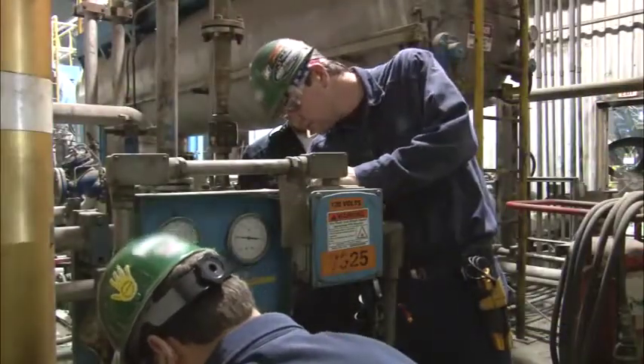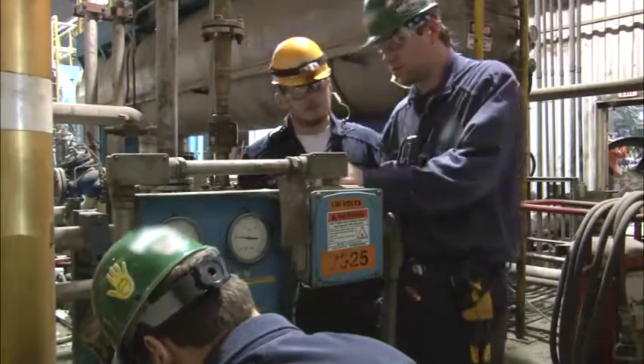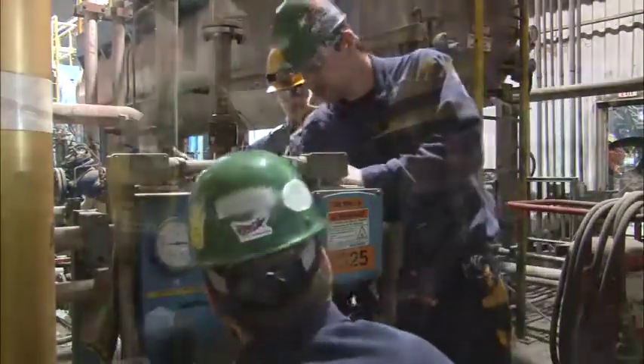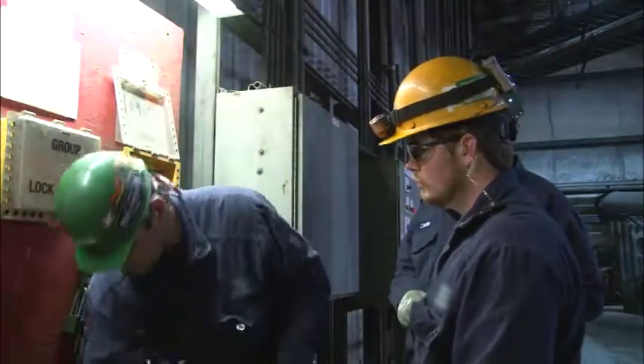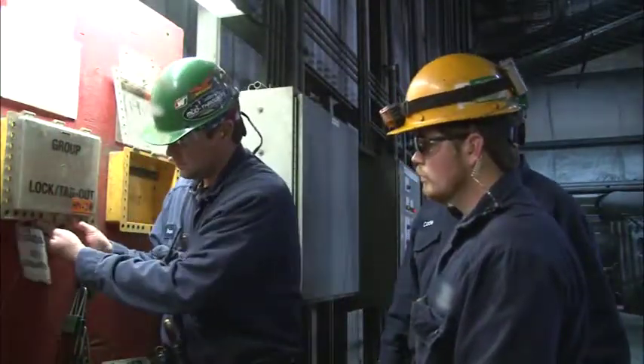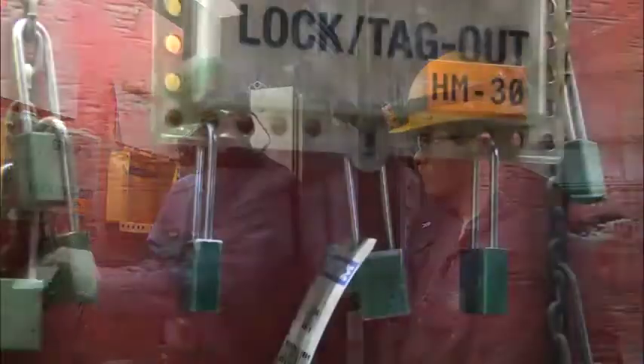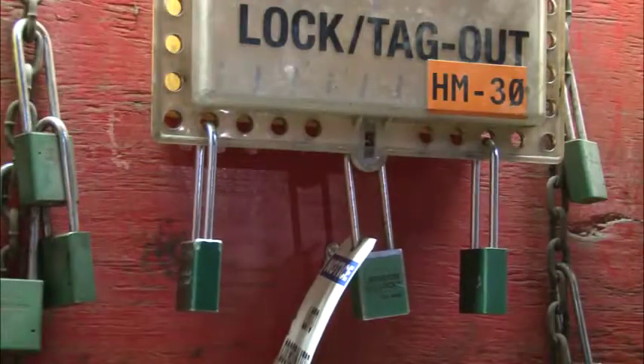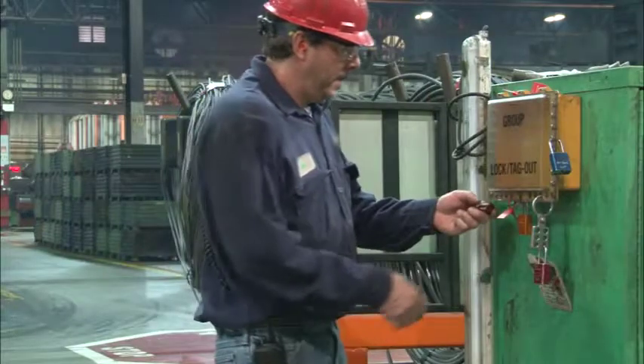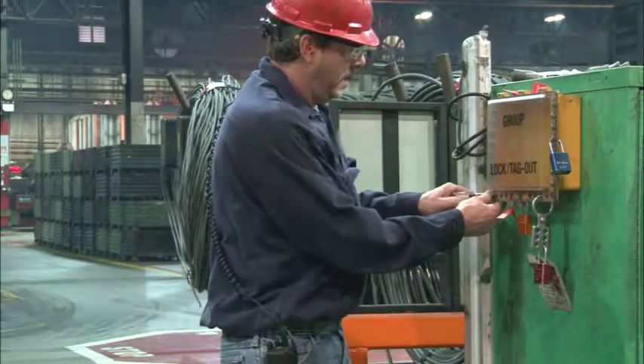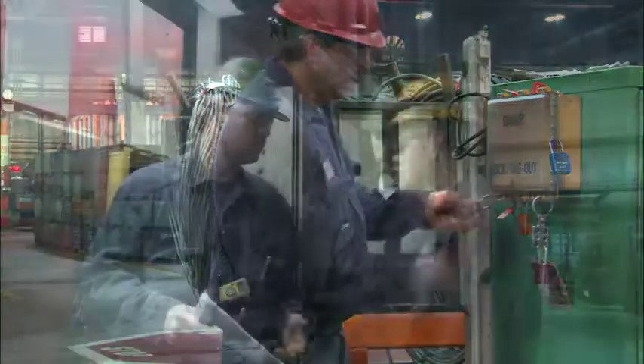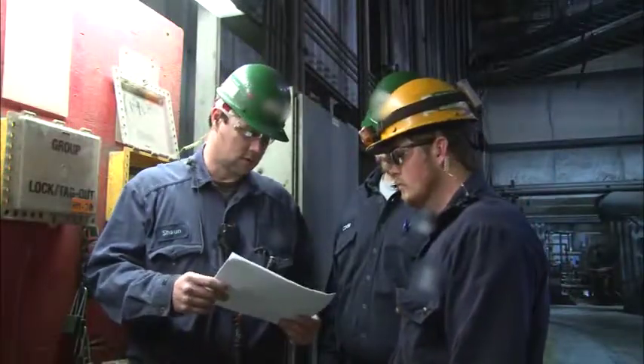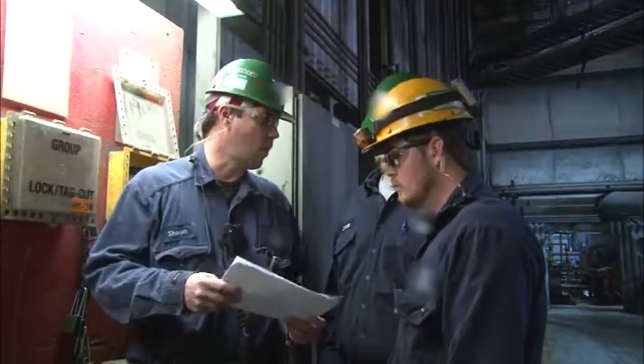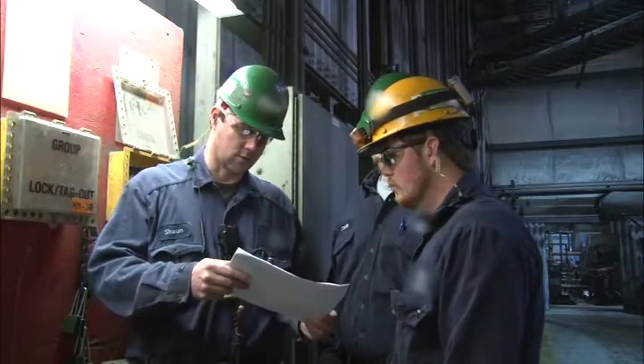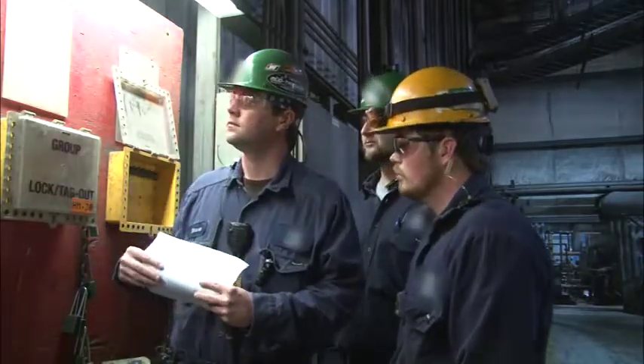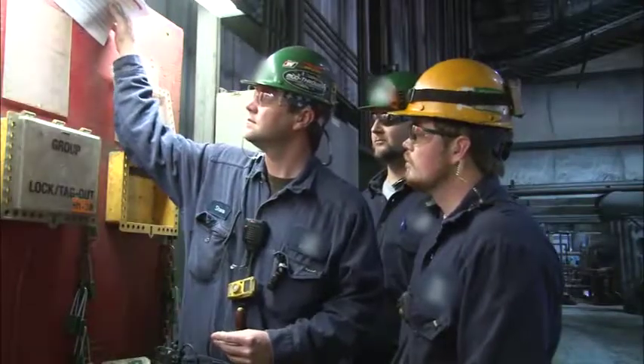A group lockout is performed whenever the servicing or maintenance is performed by a group of employees. In a group lockout situation, the employer must develop and implement an energy control procedure that provides each employee with the same level of protection. Therefore, this situation is often more complex than servicing or maintenance performed by an individual. As a result, group lockout or tagout operations typically require more coordination and communication, which is particularly important when more than one craft or department is involved to complete the task.